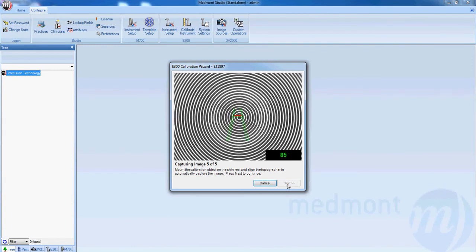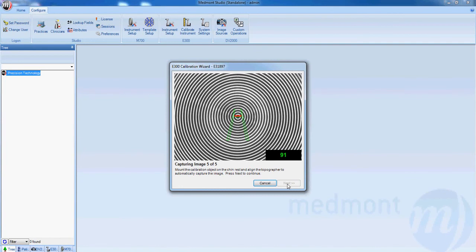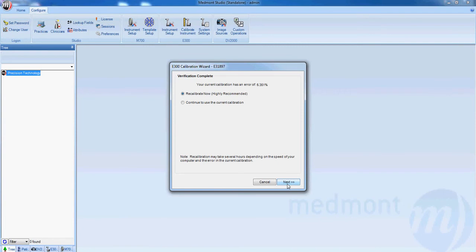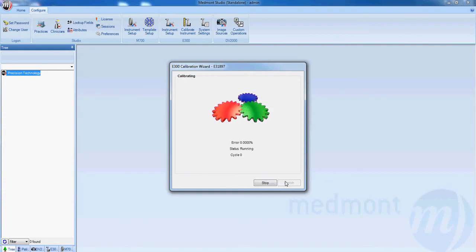Once those 5 readings are done, the instrument can determine the error that presently exists and how to correct for it. When the calibration window brings up the option to calibrate now or continue to use the current calibration, if this is the first time you've used your Medmont topographer, select recalibrate now and next. The calibration will run from 5 to 30 minutes. Allow it to complete prior to using your Medmont topographer.